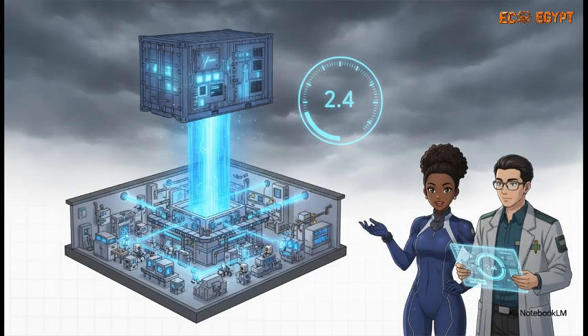And this brilliantly illustrates how we arrive at one of our most critical operational metrics, autonomy. If we take that usable energy, the 1,204 kilowatt hours, and divide it by our facility's peak demand of 500 kilowatts, we get exactly 2.4 hours. Practically speaking, this means if a massive storm rolls in and blocks the sun during a peak load event, the facility can run purely on battery power for roughly 2.5 hours without even thinking about touching that diesel generator.